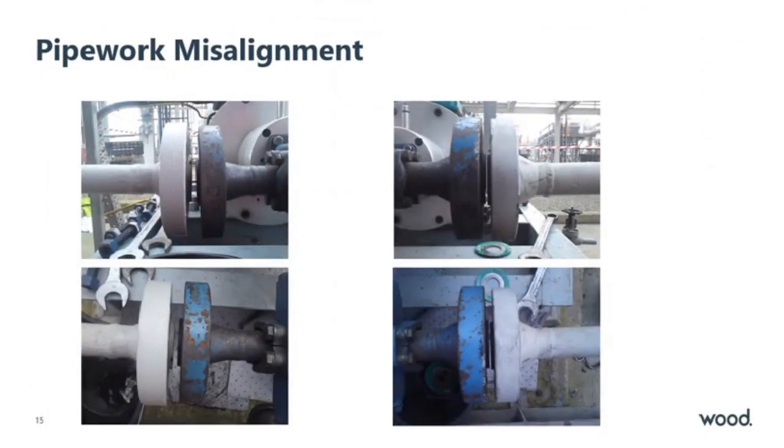There are some additional photos of bad alignment. Note there's no manipulation of the pump heads. The securing bolts to the bearing housing are not doweled to ensure that the pump goes back in the same place as before. The closing spools, the blue ones, are only 4 inches long, so they have flat face interconnections with the pump body. So how could that be wrong? It has to be something else.